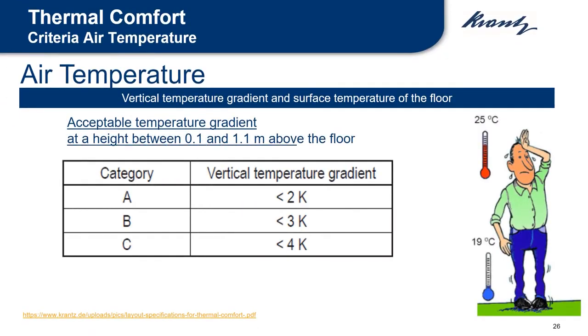Also, the vertical temperature gradient and the surface temperature of the floor are important influencing factors for the thermal comfort, energy efficiency, and the selection of the optimal ventilation system. For example, the current standards recommend a temperature difference of up to 3 Kelvin per meter between the head and the feet of a person according to category B.